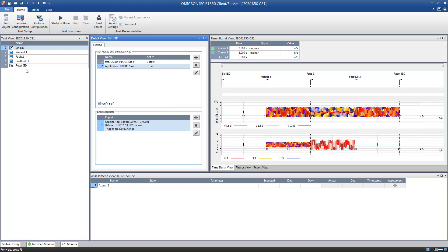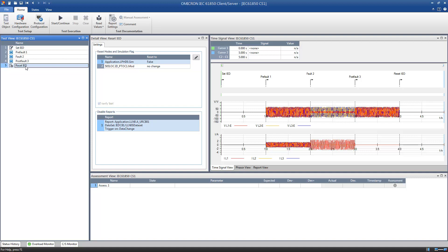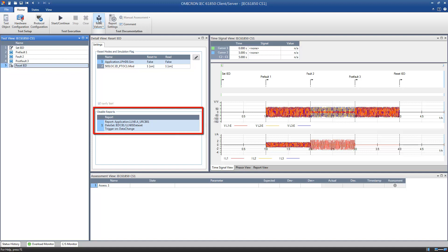Similar to the state Set IED, there is a state Reset IED at the end of the test procedure. Use this state to ensure that the IED is set back to its original condition after the test. For better orientation, you can retrieve the state of the IED before starting the test. Furthermore, the state Reset IED ensures that reports enabled in the state Set IED are automatically disabled at the end of the test.